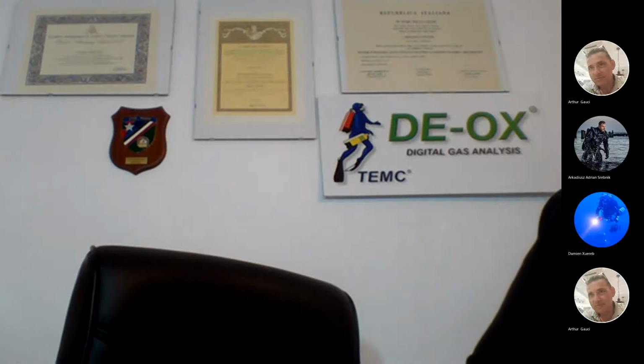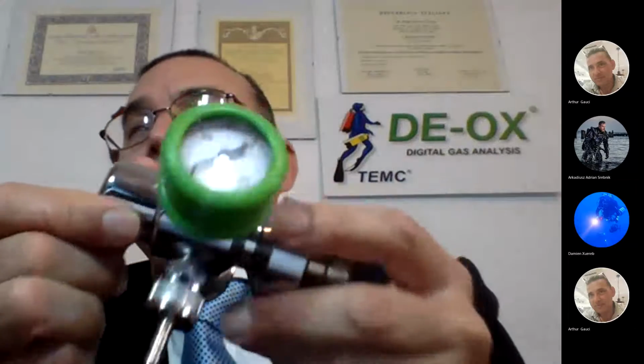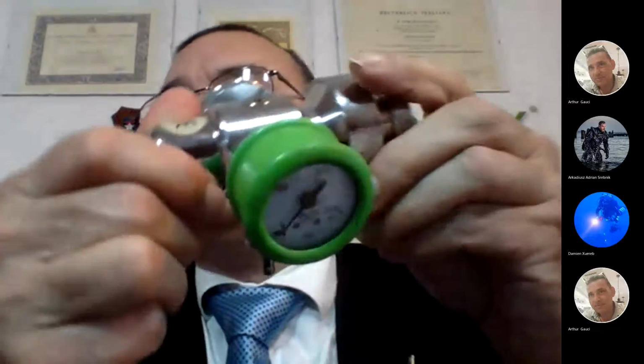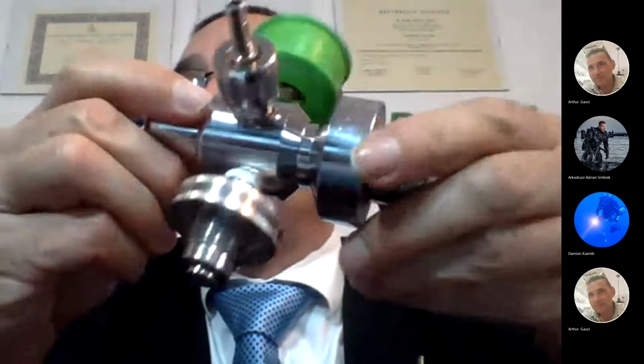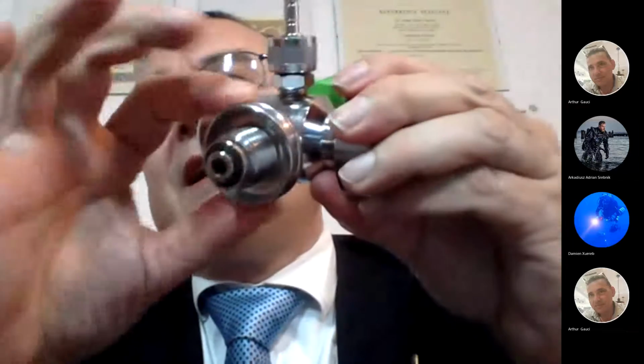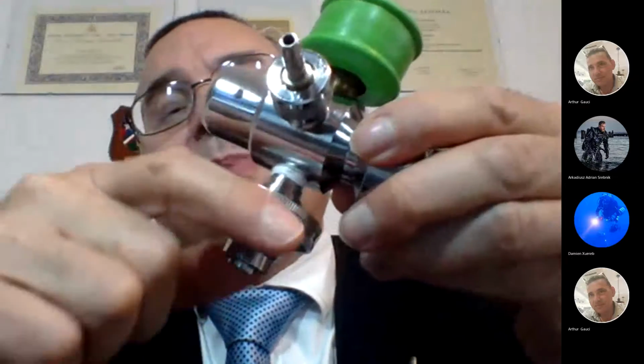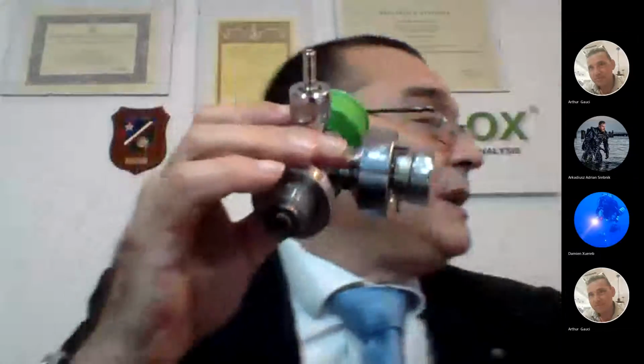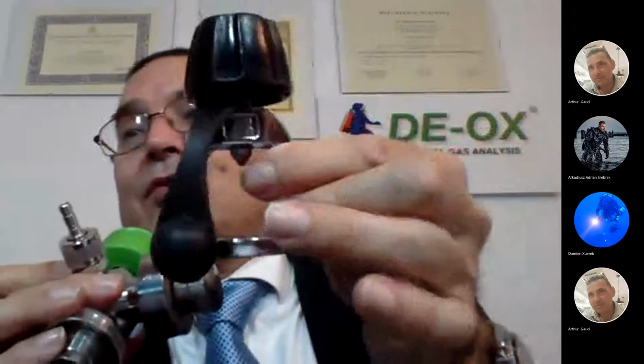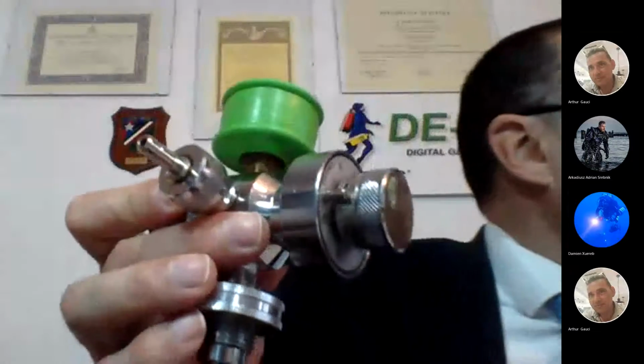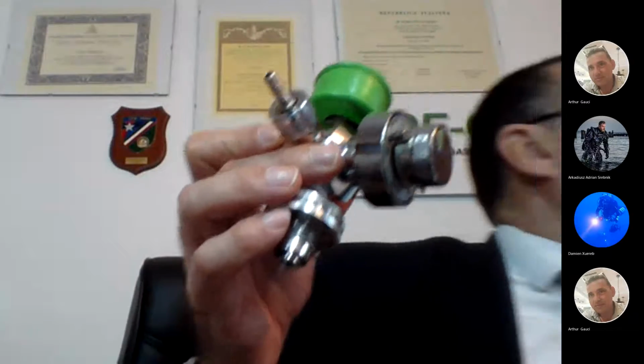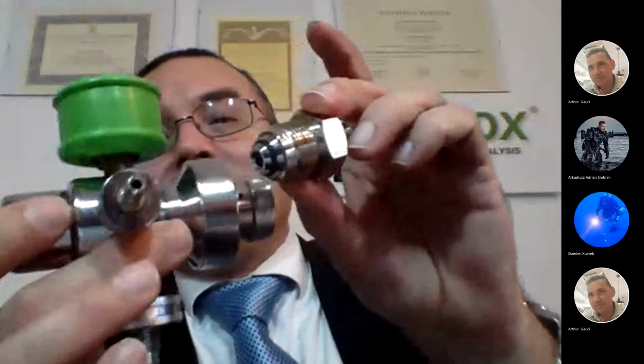Another is the medical adapter. You see, this is a typical flow meter for the oxygen cylinders. You have the possibility to replace the different heads. You can put the helium, you can put the yoke, you can put the oxygen, you can put the helium thread, and then you have a pressure gauge here, and you have also a meter here.